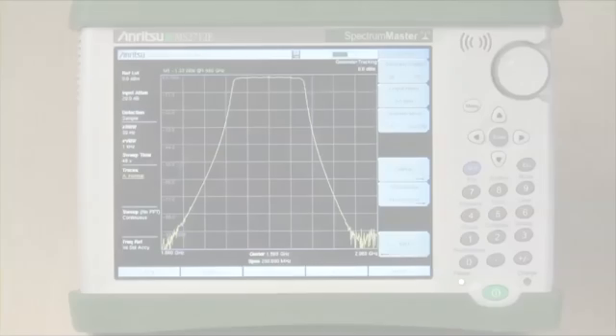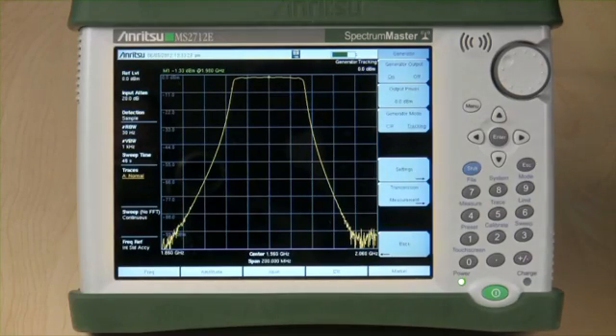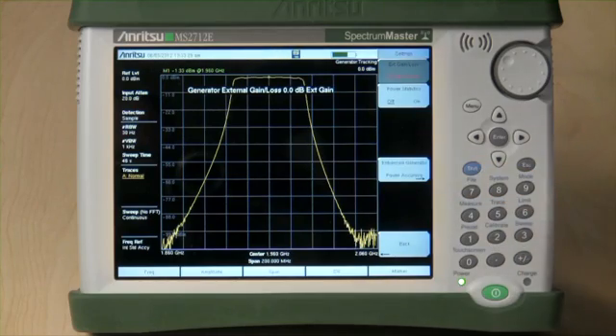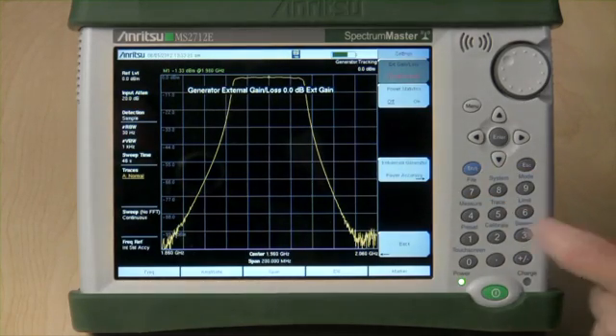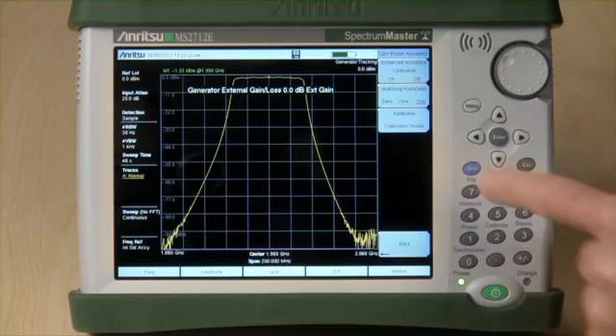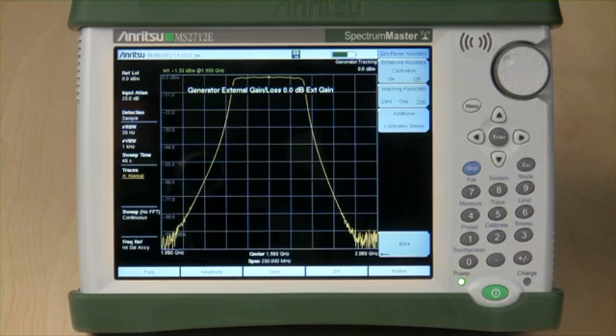To minimize the effects of temperature variations, an innovative power accuracy procedure has been included. By pressing the Setting key, followed by the Enhanced Generator Power Accuracy key, users can further minimize any amplitude level inaccuracies.